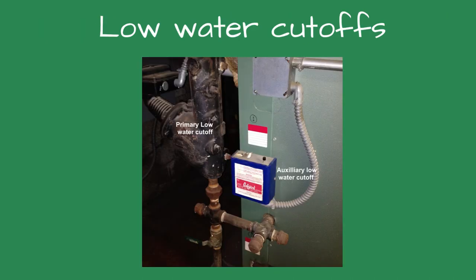Hoping to avoid a lawsuit, the boiler manufacturer hired me to troubleshoot a steam boiler in a nursing home. The boiler tripped on the low water cutoff several times a day. Most of the time it tripped on the primary low water cutoff, which is an automatic reset control, and sometimes it tripped on the auxiliary low water cutoff, which is a manual reset control.